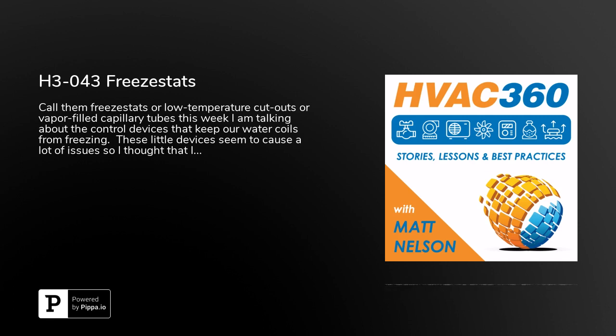So first question you've got to ask: where do you put the body of the Freezestat device? Well, you want to put it on the top of, not literally the top, but basically on the vertical face of the unit. You want to put it up pretty high. Obviously, you want to have the capillary tube coming out of the bottom of it, so you want the capillary tube going down. But you want to place it about as high as you can on the outside of the casing.